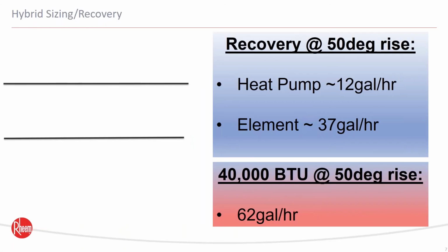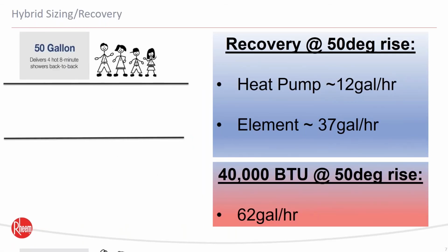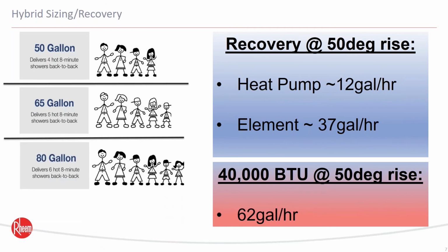Physical installation, of course, before you install it, you want to make sure that you're installing the right equipment. A 50-gallon heat pump water heater is not equivalent to a 50-gallon gas. And a lot of that has to do with the recovery. So traditionally with a heat pump water heater, it's going to have long recovery times. That's the way it's going to run the most efficient.